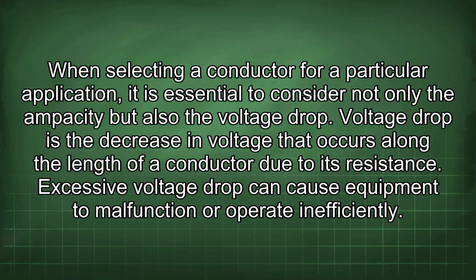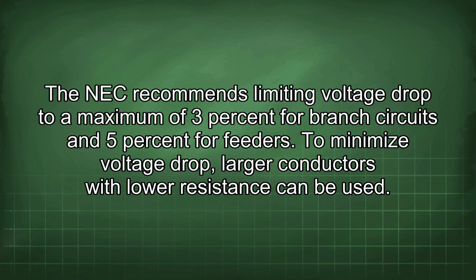When selecting a conductor for a particular application, it is essential to consider not only the ampacity but also the voltage drop. Voltage drop is the decrease in voltage that occurs along the length of a conductor due to its resistance. Excessive voltage drop can cause equipment to malfunction or operate inefficiently. The NEC recommends limiting voltage drop to a maximum of 3% for branch circuits and 5% for feeders. To minimize voltage drop, larger conductors with lower resistance can be used.